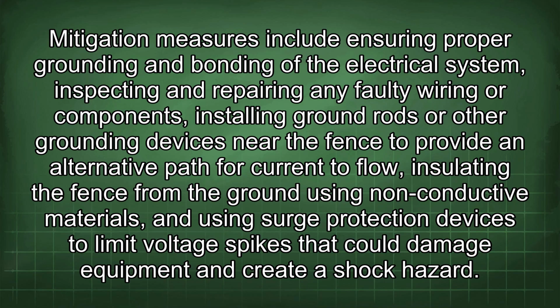Mitigation measures include ensuring proper grounding and bonding of the electrical system, inspecting and repairing any faulty wiring or components, installing ground rods or other grounding devices near the fence to provide an alternative path for current to flow, insulating the fence from the ground using non-conductive materials, and using surge protection devices to limit voltage spikes that could damage equipment and create a shock hazard.